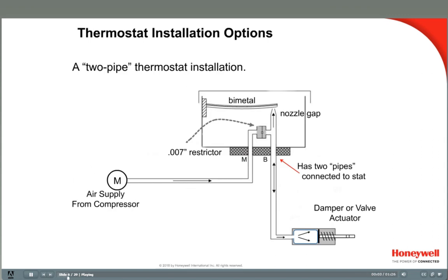This diagram is of a two-pipe thermostat installation. In a two-pipe installation, the main air tubing and the branch line tubing are connected directly to the thermostat. The ports on the back of the thermostat are marked M and B. Notice that the restrictor and nozzle flapper assembly are both part of the thermostat. The air first passes through the restrictor, then to the nozzle where it is allowed to bleed off. The restrictor limits the supply of air to the thermostat to no more than can be bled off by the nozzle, making it possible for the thermostat to control the branch line pressure.